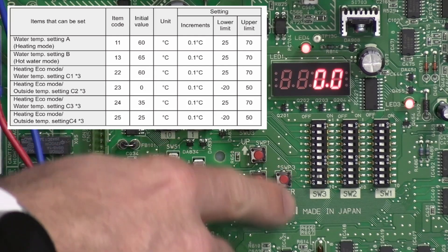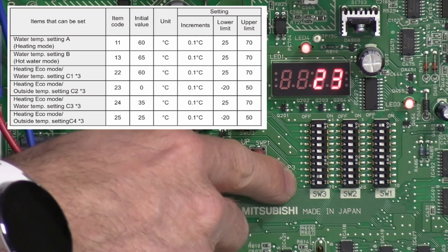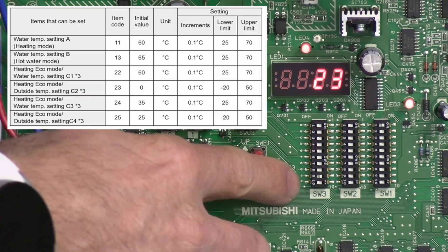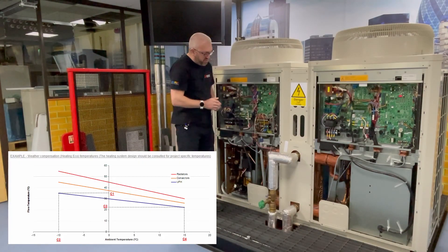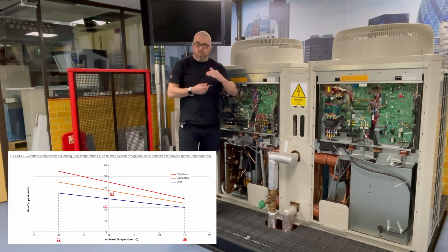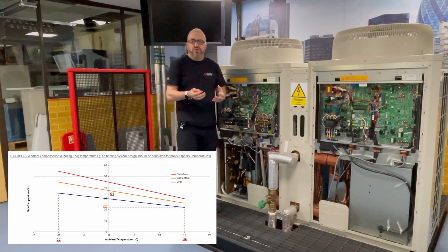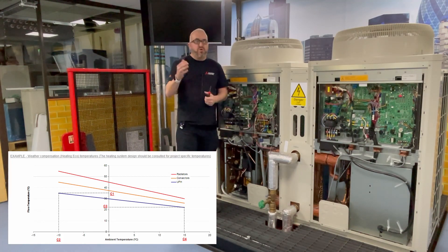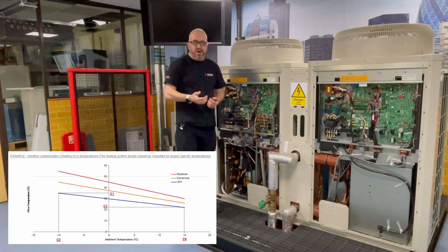So the next one we need to set the other end of the scale, so it's item 24. We now need to set the lower water temperature, so the minimum water temperature the system is going to operate when it's quite a mild or warm day outside.